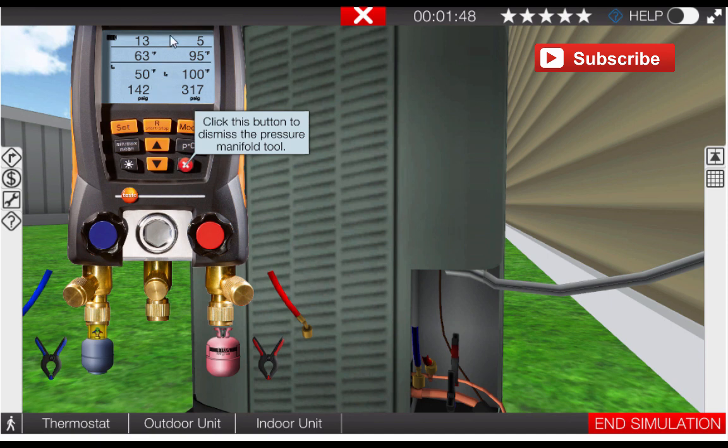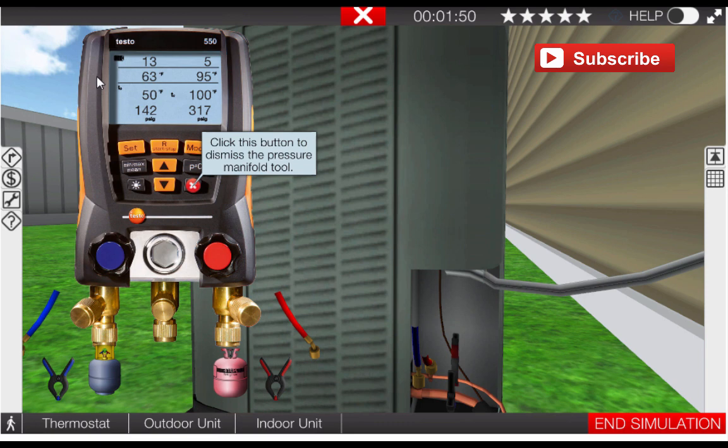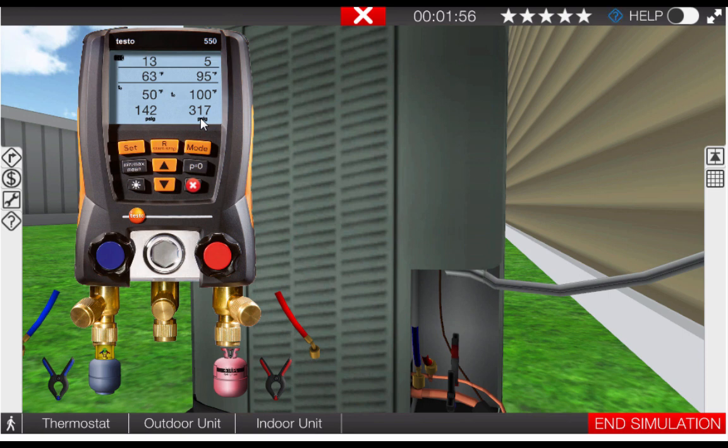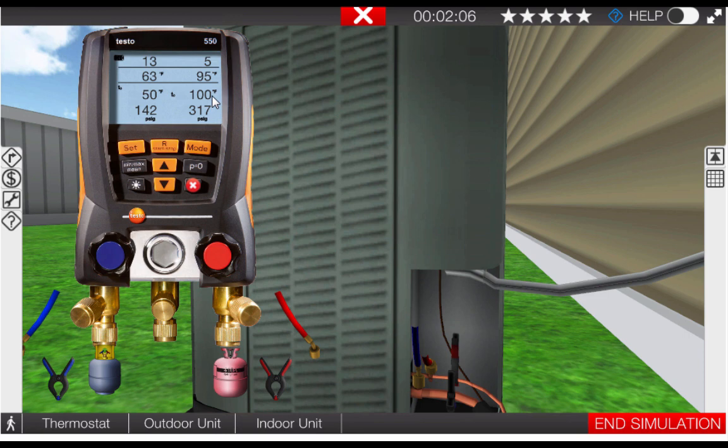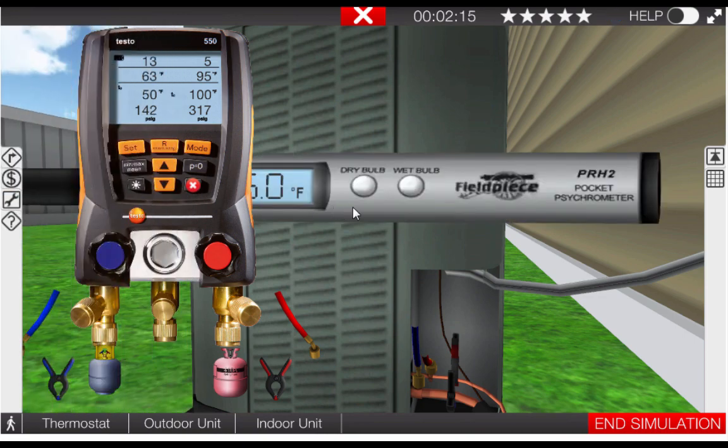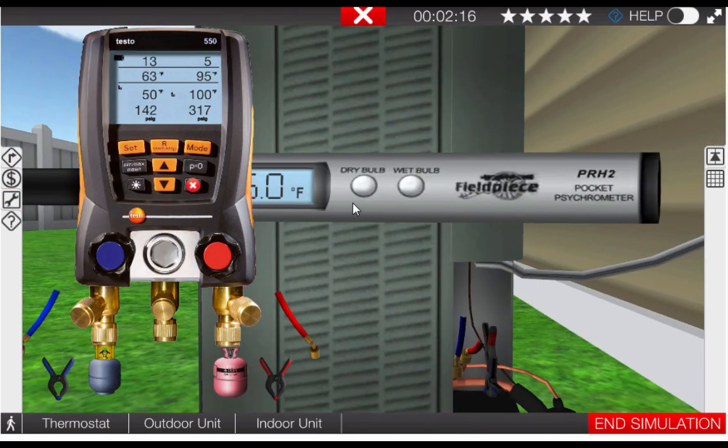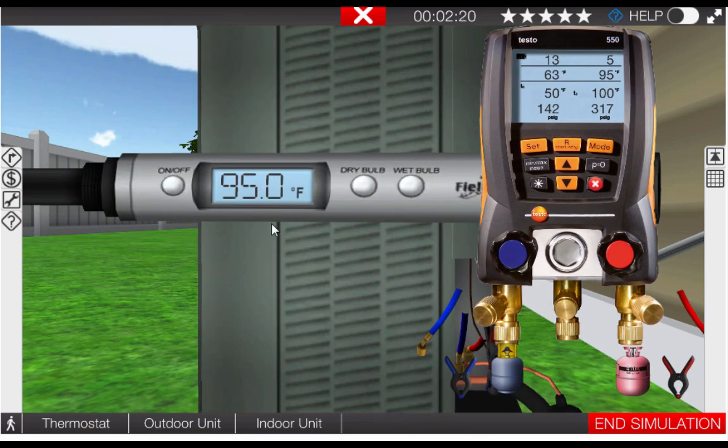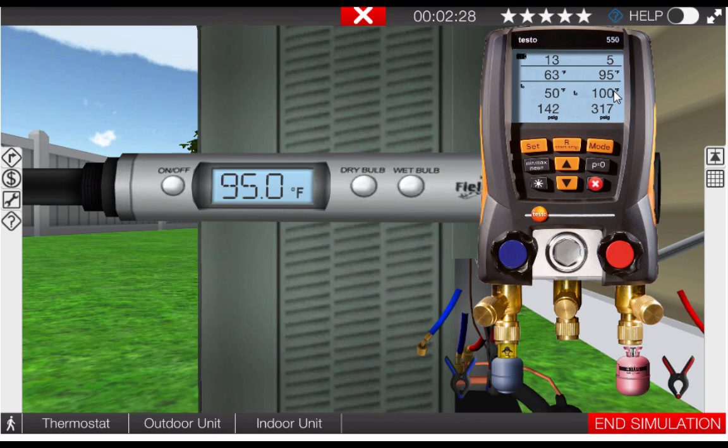Let's take a look at what we've got here. If you look at the pressures the high side pressure is 317 psig which converts to a condensing temperature of only a hundred degrees. The condensing temperature under normal operating conditions should be approximately 20 degrees above the outdoor ambient temperature. Let's check the outdoor ambient temperature by taking the digital psychrometer out of the toolbox. And we can see here if we move the gauges out of the way that it is in fact 95 degrees outside. So basically what we should have here is a condensing temperature of about 115 degrees Fahrenheit which would result in a discharge pressure or high side pressure of 391. We're well below that mark.